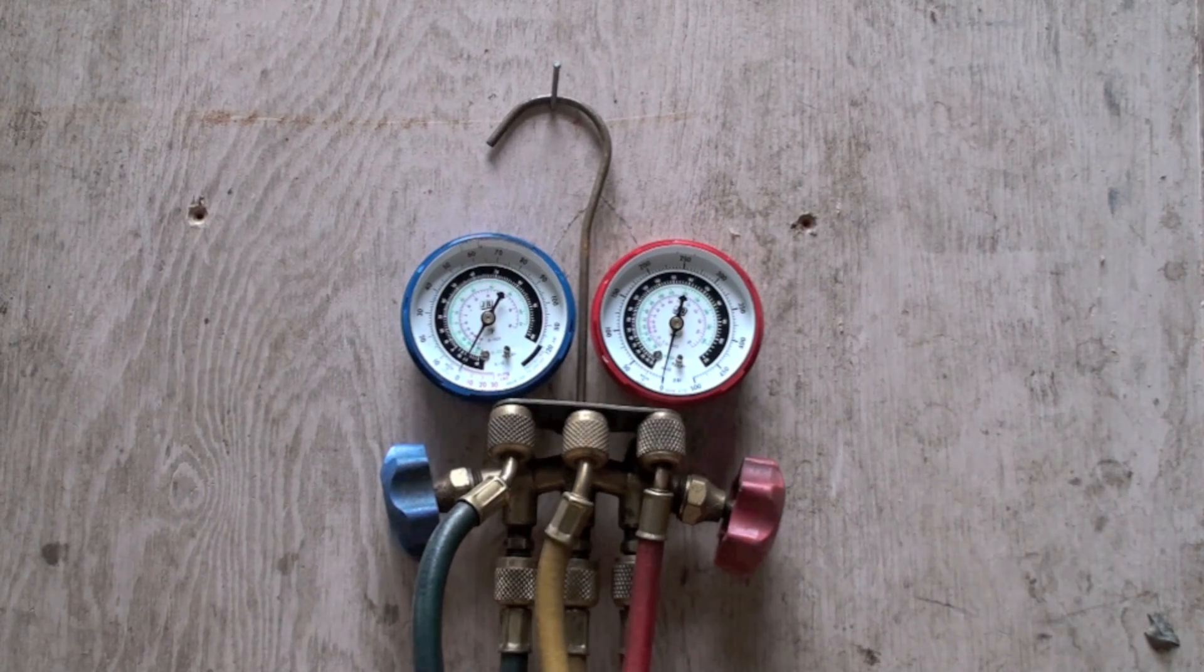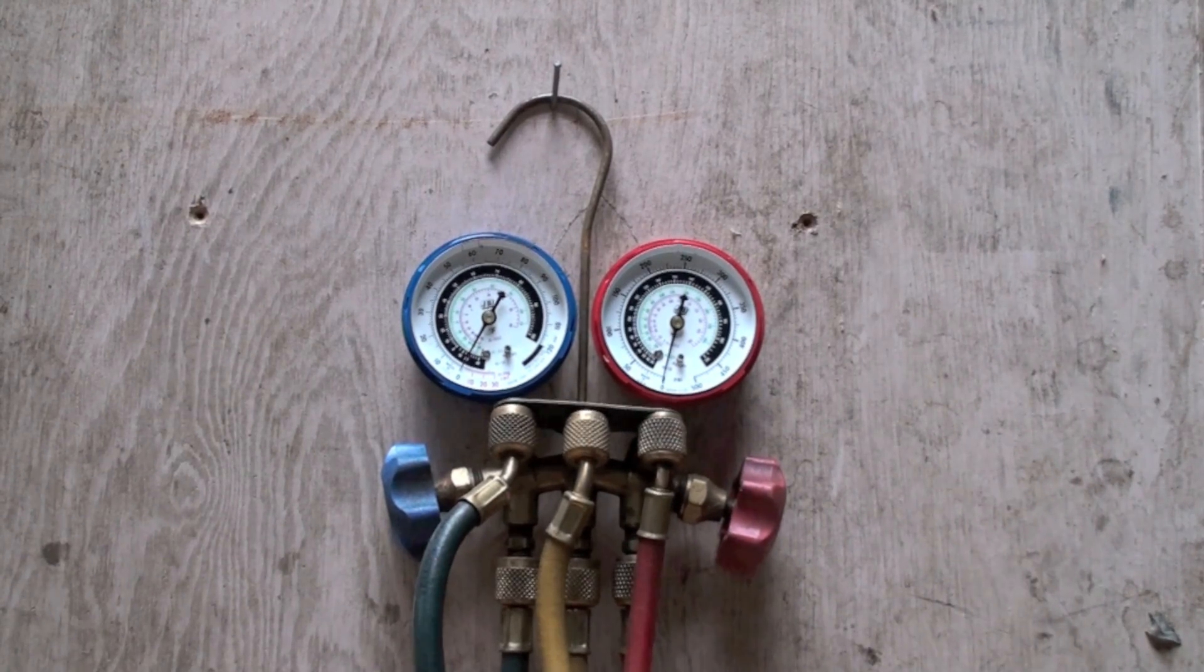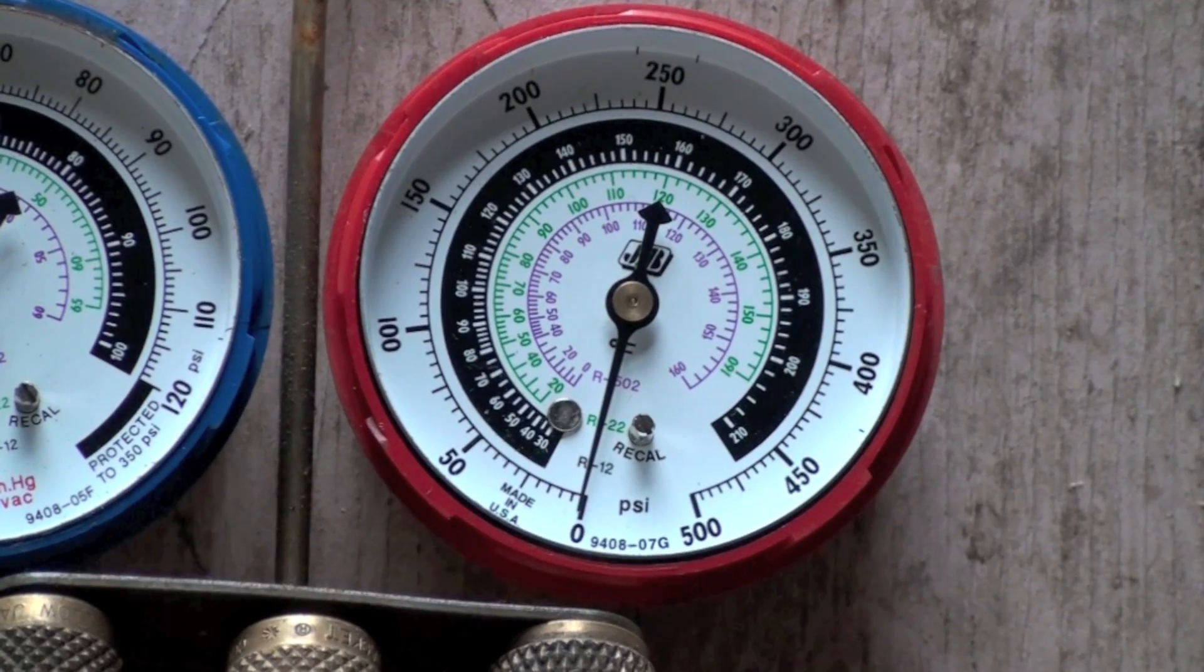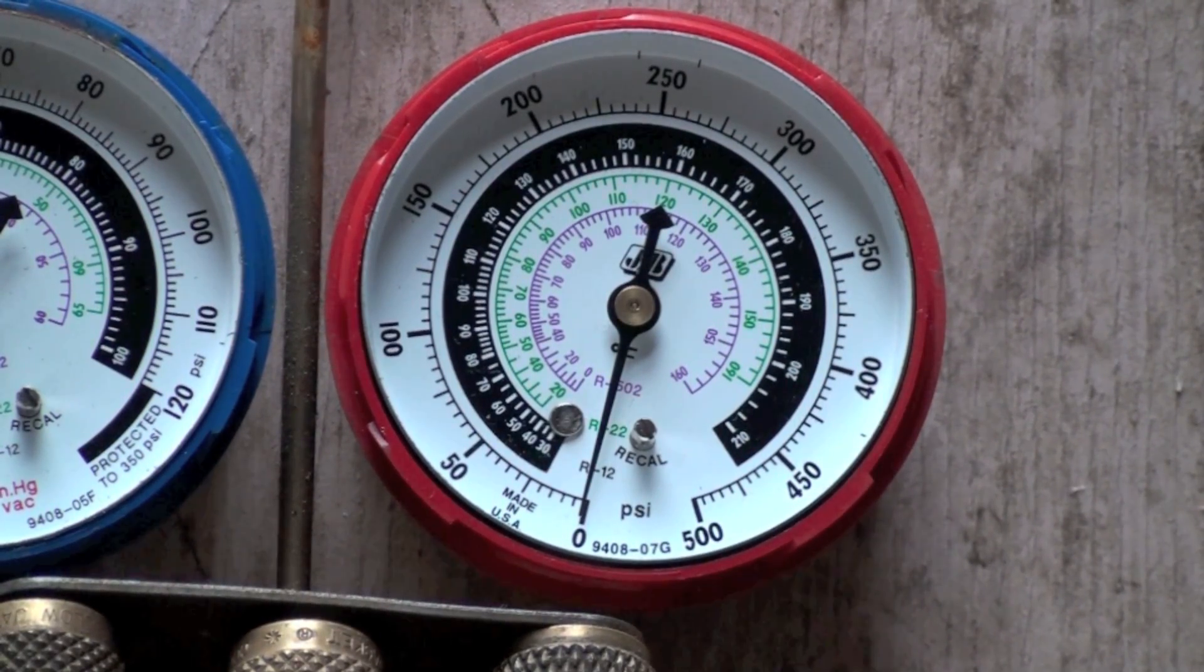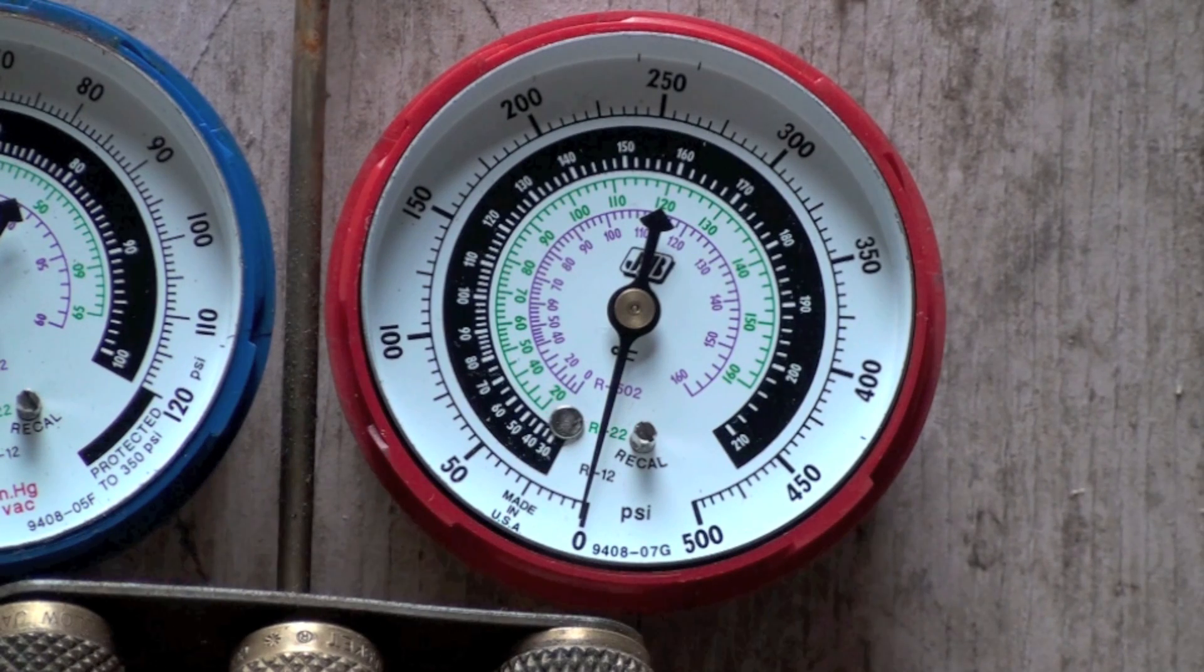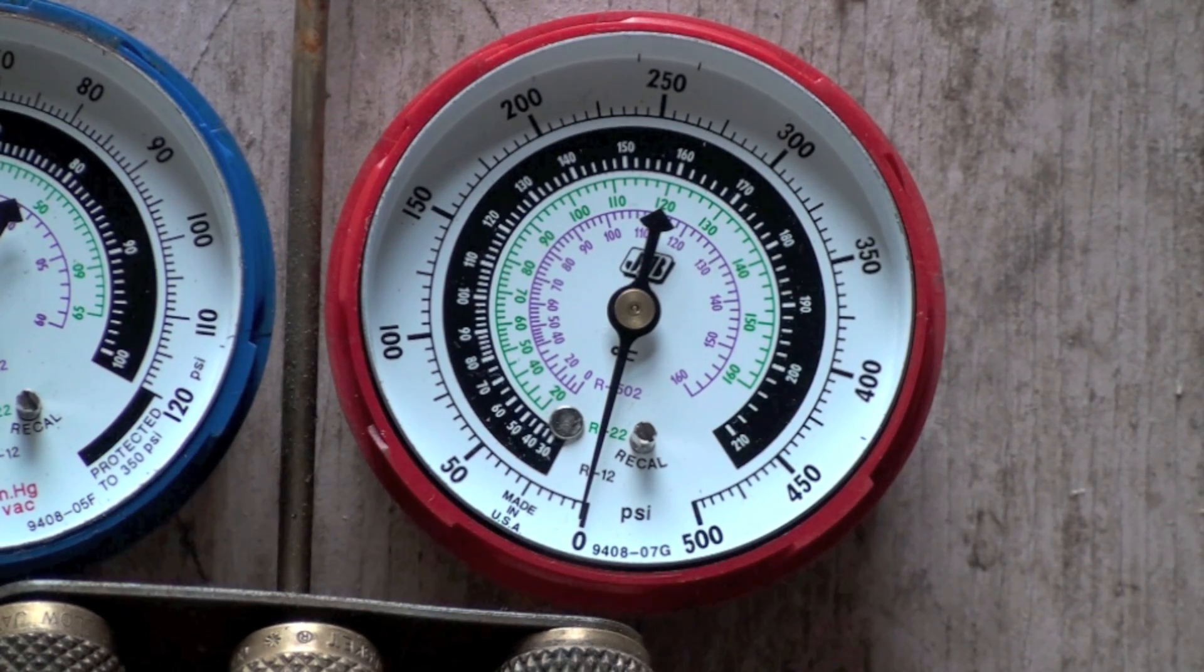Now this is a gauge pressure gauge. It is showing zero psi, that would be zero psig, and that's at atmospheric pressure. So it should always read zero when there's no pressure in the manifold, but that actually is just under 15 pounds absolute pressure.